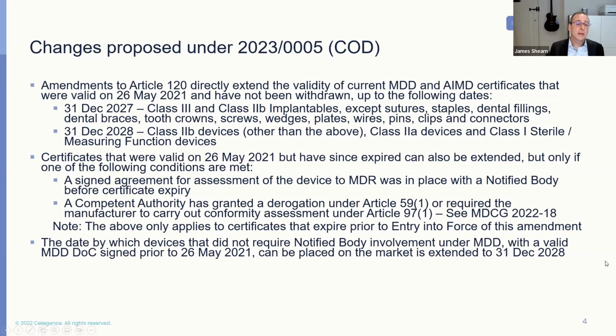Also included is the date by which devices that did not require notified body involvement under the MDD, so primarily Class 1, that had a valid MDD DOC signed prior to the 26th of May 2021 can be placed on the market up until the 31st of December 2028.